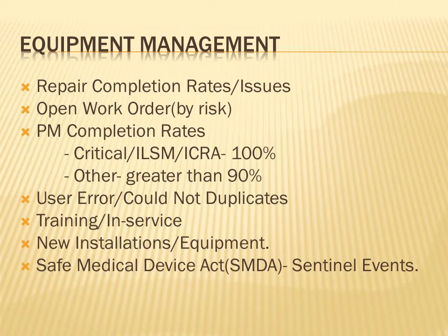Open work orders, I put in here by risk. Certainly, if we have an open work order for checking some toasters or checking some microwaves, it may not be as critical as open work orders and repair and services on some utility systems or medical gas systems, or equipment that functions inside of, let's say, our OR or other revenue generating environments or patient care environments. So by risk, I think that's a more critical piece, and probably even just high risk equipment. Open work orders is what should be reported up to safety committee.